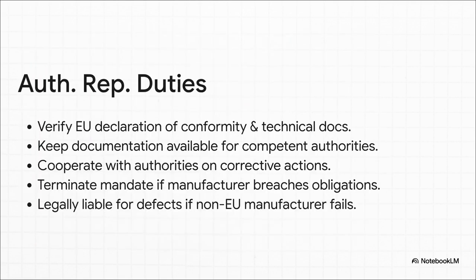Now this is where things get really interesting, because we start talking about shared liability. The authorized representative's job is to verify your documentation and act as the main point of contact for EU authorities. But here's the absolute kicker. If that non-EU manufacturer fails to comply, the authorized representative is legally liable for defective devices, right there alongside them. They are on the hook.